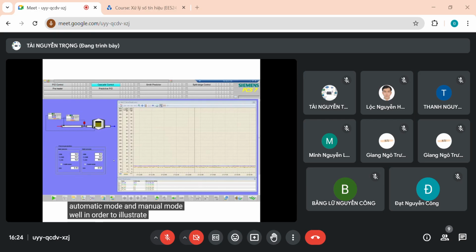Well, in order to illustrate the concepts of automatic mode and manual mode and output tracking, I'm going to use another system here, and it's a cascade system. I will not go too much into the details because this process will be used when I will be talking about cascade control. But it suffices to say here that you have an outer loop and an inner loop, or a master loop here and a slave loop. Okay, so the master loop is controlling the temperature over here, and it is setting the flow of fuel here. And the fuel flow is controlled using this slave control by acting on the control valve over here.